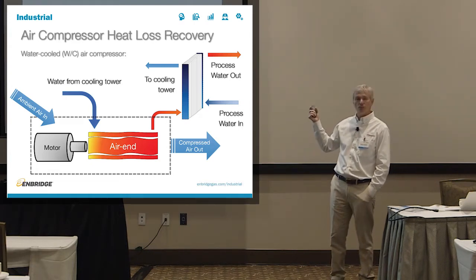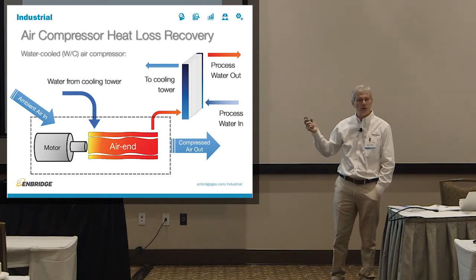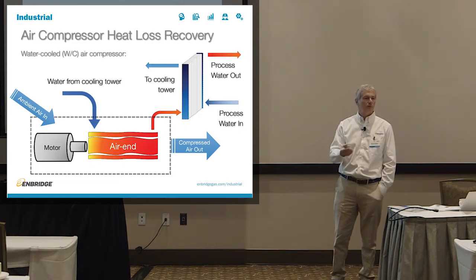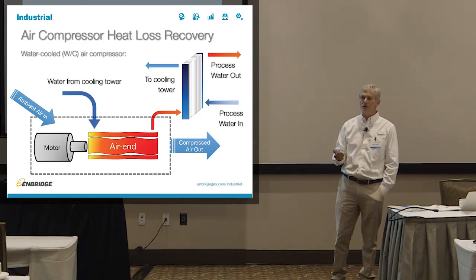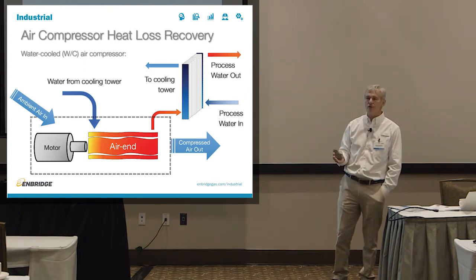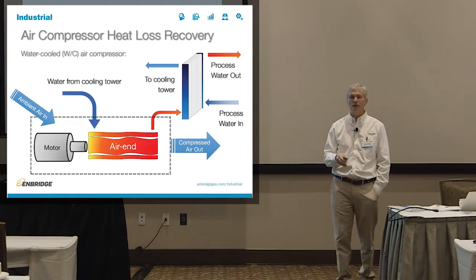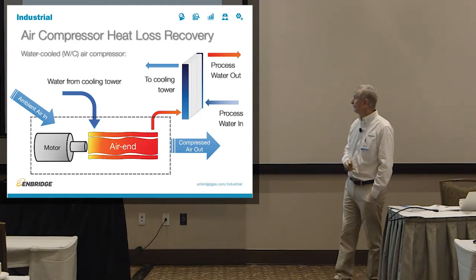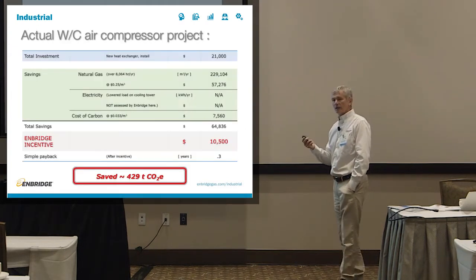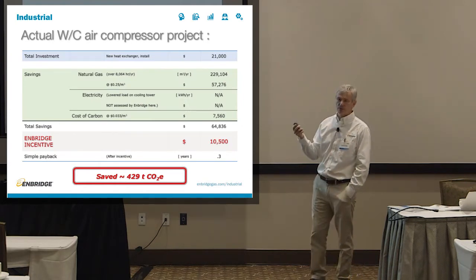I like to use process water streams because they're constant. If you put a glycol loop, if you put an HVAC application, we get about half a year's worth of energy savings. If you use a process that runs all the time, you get a full year's worth of energy savings. So if you can find a process sink, use it. Again, an example of an actual project that we've done with a customer.